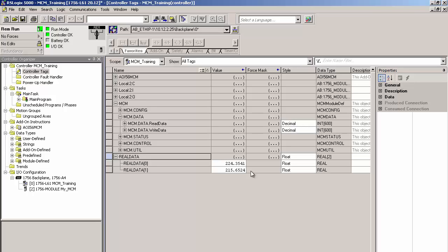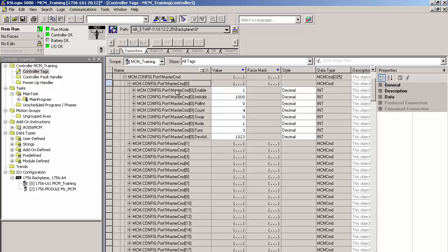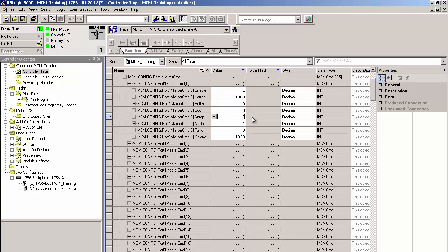Now, the Modbus protocol does not specify what order the words of double integers or float values should be transmitted in. Different industrial vendors order them differently. If they're read in the wrong order, the data in the MCM will not appear properly. If this happens, all you have to do when you set up the command is enter a 1 for swap. This will swap the word order when you're dealing with 32-bit values. There's also a code for swapping bit order and words and bits.